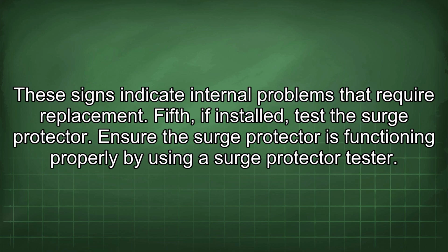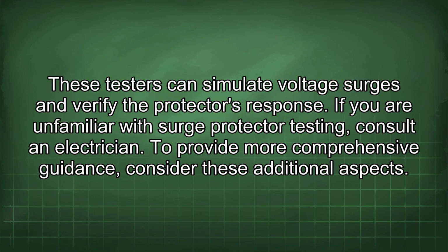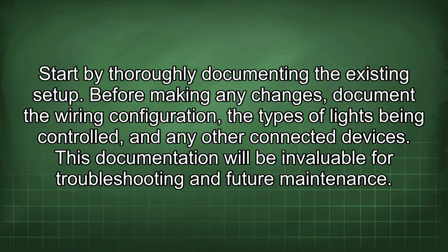Fifth, if installed, test the surge protector. Ensure the surge protector is functioning properly by using a surge protector tester. These testers can simulate voltage surges and verify the protector's response. If you are unfamiliar with surge protector testing, consult an electrician. To provide more comprehensive guidance, consider these additional aspects. Start by thoroughly documenting the existing setup. Before making any changes, document the wiring configuration, the types of lights being controlled, and any other connected devices. This documentation will be invaluable for troubleshooting and future maintenance.